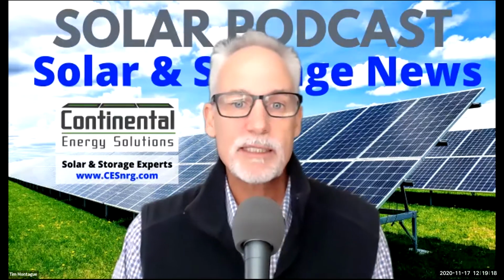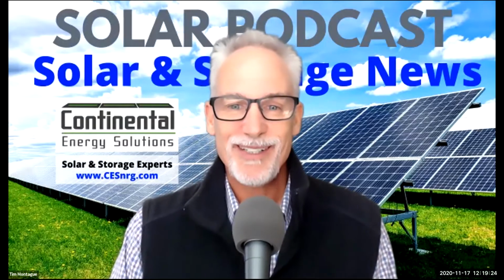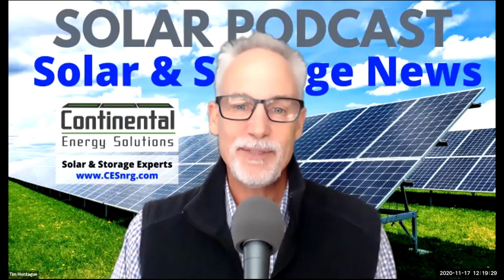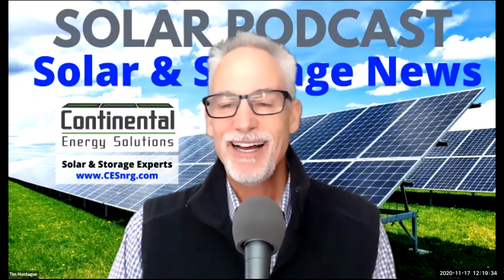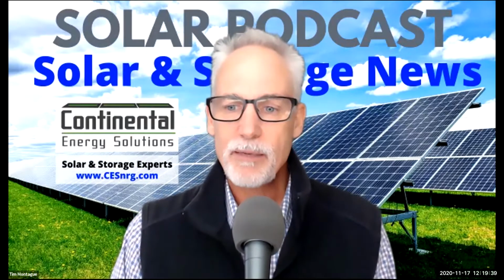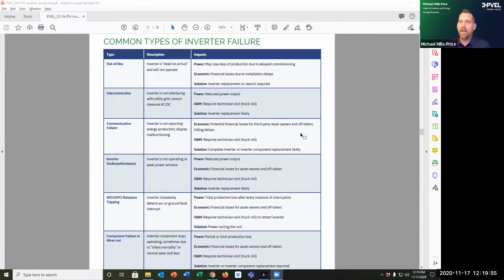It starts with out of the box. And surprisingly, we do have out of the box failures. You would think that would be like a non-existent thing. You would think that they would have to have passed some tests at the factory. I guess the damage could occur in shipping, but yeah, let's talk about inverter failures. How do they fail? If you pull that back up, Tim, that table. So as you mentioned, all inverters actually do get tested, or are supposed to get tested, as part of the production line sequence tests prior to shipping from the factory. But things can happen, right?